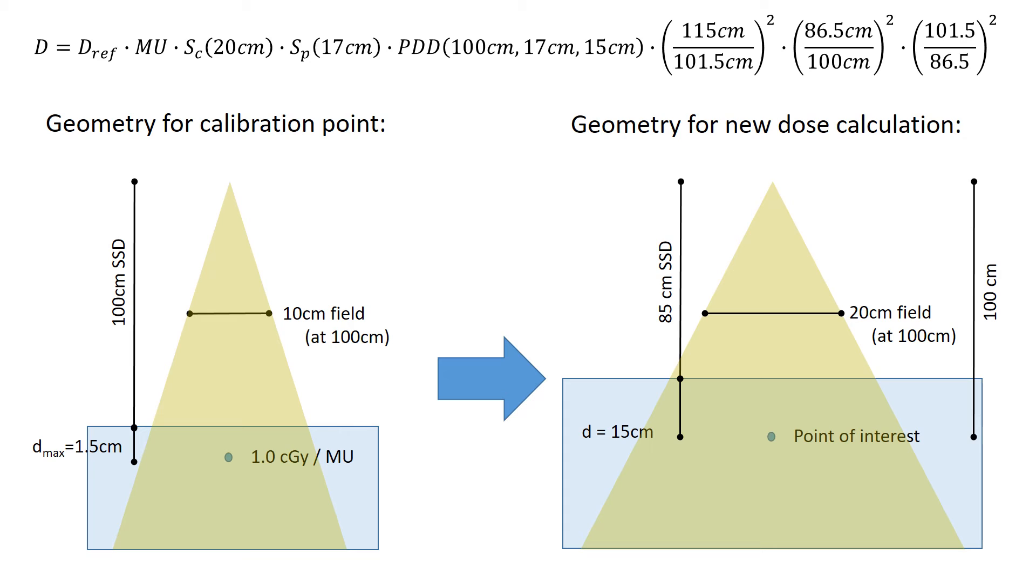And with that, we have all of our factors that we need. We can get our collimator scatter factor for a 20 field size, our phantom scatter factor for a 17 field size, our PDD for a 17 field size and a 15 cm depth, and then we have our f-factor input, and then our inverse square correction. And that will take us from this calibration geometry on the left to our new geometry on the right.